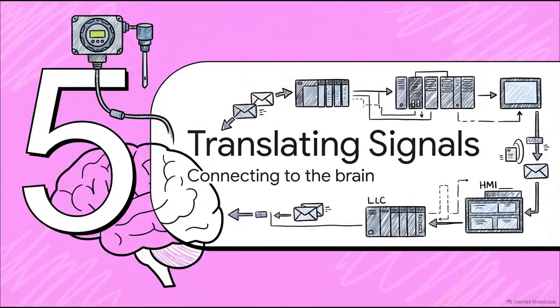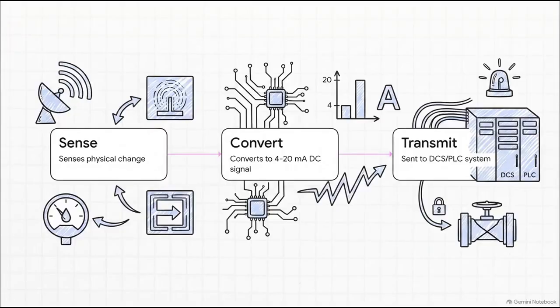Section 5. Translating signals to systems, connecting the sensor to the plant's brain. So think of the transmitter as a universal translator. In step 1, it senses the physical change. Maybe that's a radar echo, a pressure drop, or a shift in capacitance. In step 2, the onboard electronics perform a crucial conversion, turning that physical reading into a standardized 4 to 20 milliamp DC electrical signal. Finally, in step 3, this signal is sent over the wires to the DCS or PLC. Those are the central computer brains of the plant, triggering alarms and automatic interlocks the second they're needed.